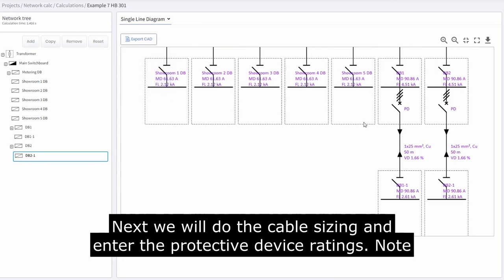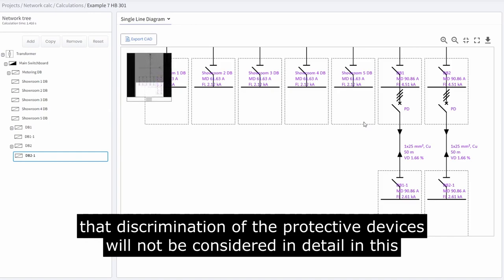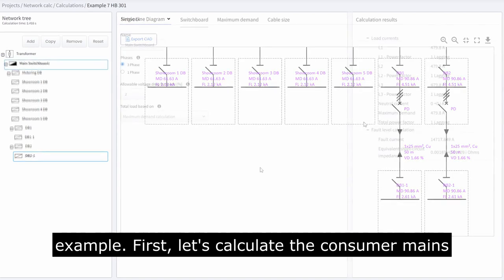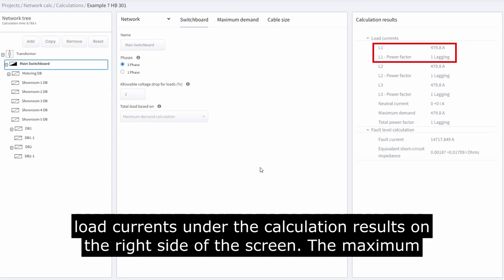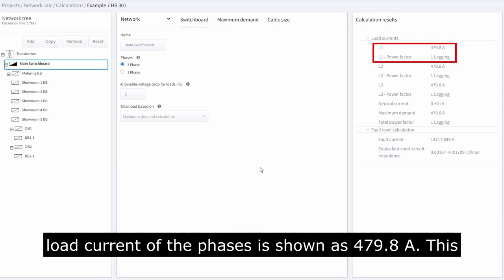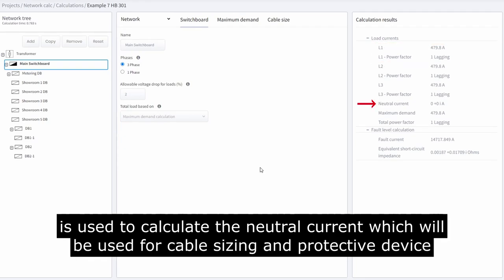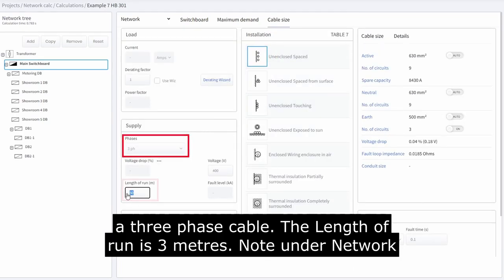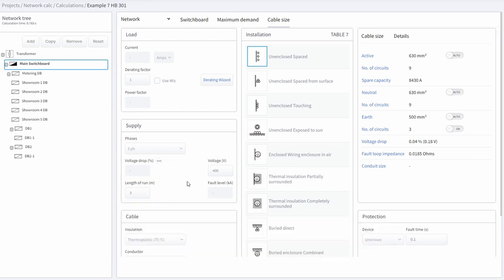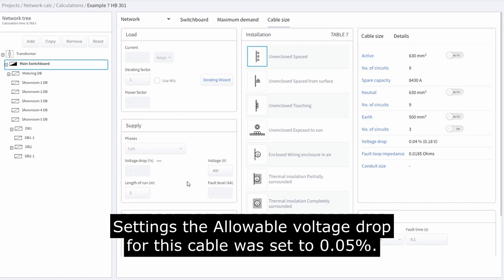Next, we will do the cable sizing and enter the protective device ratings. Note that discrimination of the protective devices will not be considered in detail in this example. First, let's calculate the consumer's mains cable size. Select the main switchboard from the network tree. Note the load currents under the calculation results on the right side — the maximum load current of the phases is shown as 479.8 amps, which is used to calculate the neutral current for cable sizing and protective device selection. Go to the cable size tab. The consumer's mains cable is a three-phase cable with a length of run of 3 meters. Note that under network settings, the allowable voltage drop for this cable was set to 0.05%.